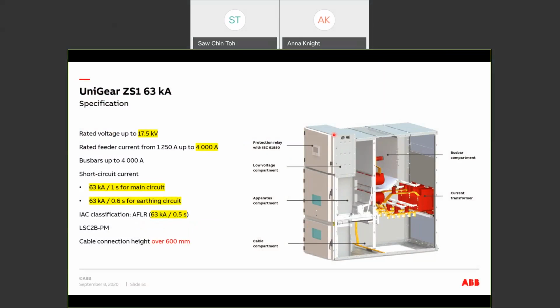The panel layout, as you can see, is quite similar to UniGear ZS1. We have the LV compartment, the apparatus compartment to house the withdrawable breakers, the busbar compartment, and this is the cable compartment with cable termination and the current transformers. The only difference is that this cubicle is going to be deeper compared to the standard UniGear ZS1 cubicle.